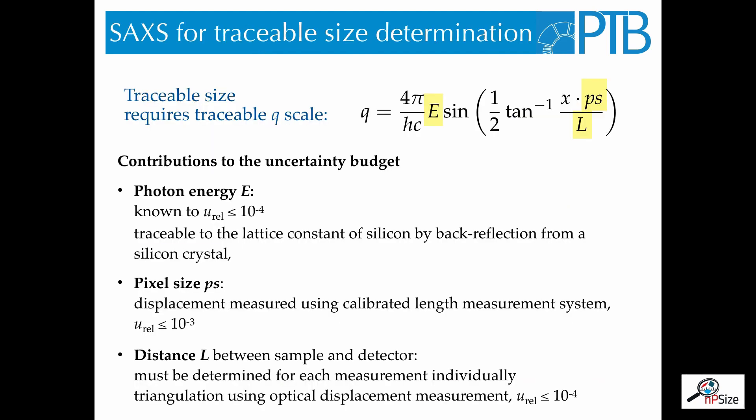Now, in order to get a traceable size determination by SAXS, we first need a traceable q-axis of our scattering curve. In the formula for q, there are three input quantities, namely the photon energy, the pixel size of the detector, and the distance between sample and detector.